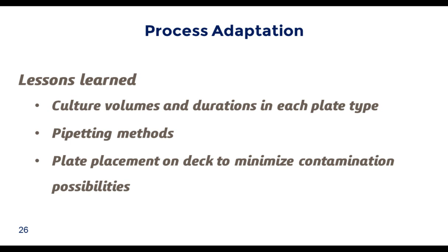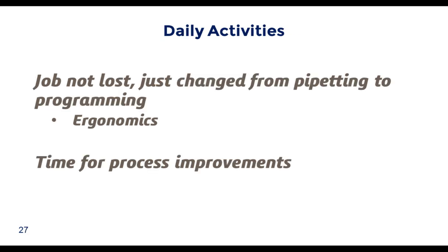The workflow must be adapted to the automated platform. Lessons learned include: culture volumes and durations for optimal growth in each plate type were determined; pipetting methods were written and optimized for speed, incorporating air gaps and tip touching where necessary; plate placement on deck was modified to minimize contamination possibilities; and plate locations were selected where the pipetting head crosses over the least amount of culture area. Through this process, the daily activity of a cell line developer evolves from pipetting to programming — teaching a robot how to pipet and supplying it with necessary inputs.